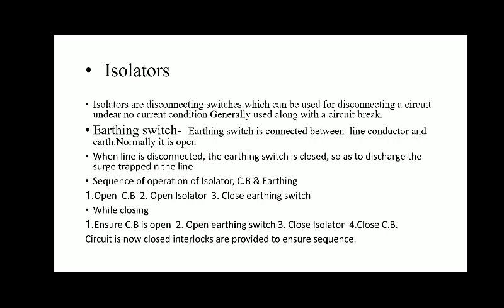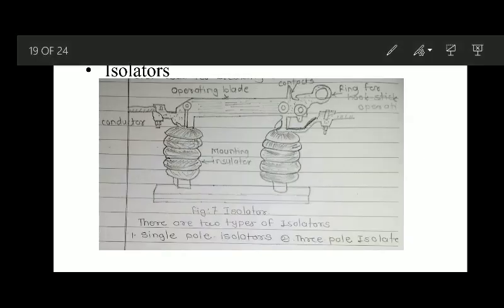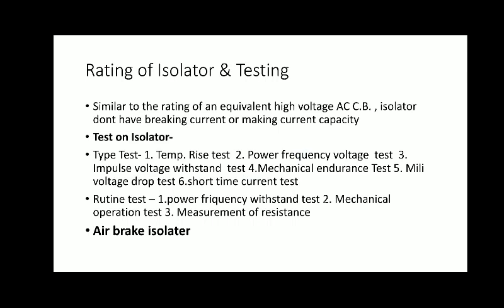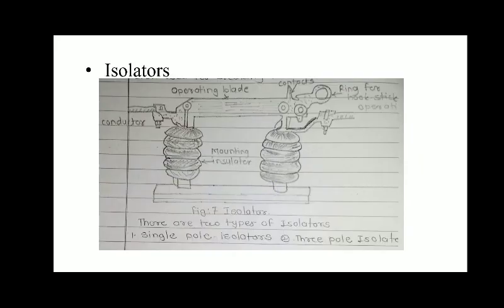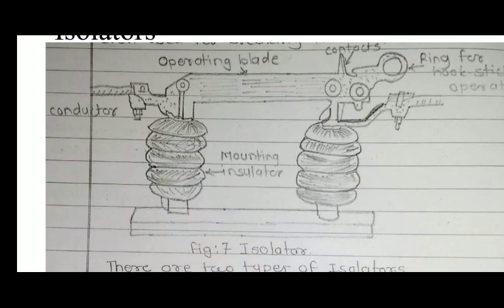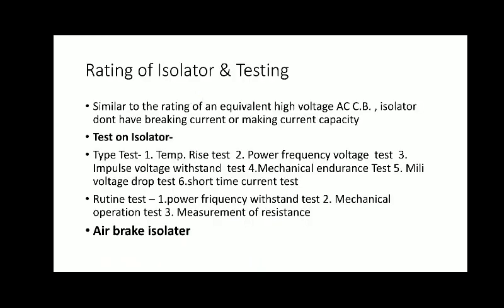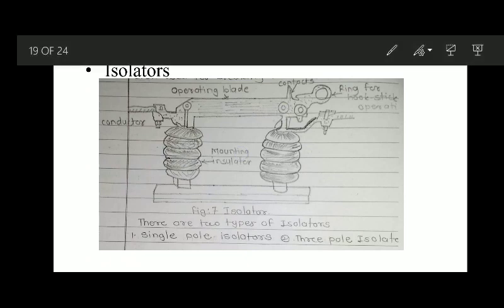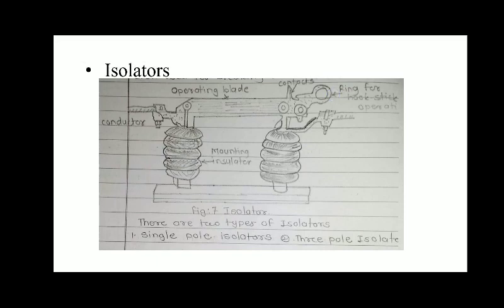Next part is the rating of isolator and testing. Before that, we see the diagram of an isolator. In this diagram, first is the incoming conductor which is connected to your isolator. This is the operating blade. Next are the contacts, and there is a ring for hook stick operation. Next there is a mounting insulator, and this is the base. So when this blade is open, your line is disconnected from prior or after connection.